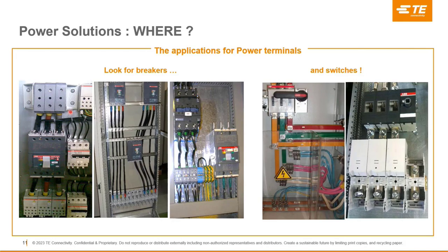In the first image, the incoming of the MCCB is used with a type of compact power block. This can also be replaced with a power terminal block if the wire is below 35 square mm, so both can be used interchangeably.